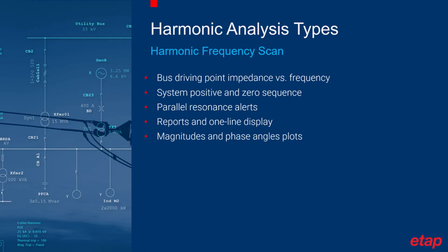One particular concern with harmonics is the resonance condition in the power system. Because of the existence of both inductive components and capacitive components in the system, at certain frequencies, resonance conditions might occur at some buses. If the resonance occurs at a bus where a harmonic current is injected into the system, an overvoltage condition will be observed.